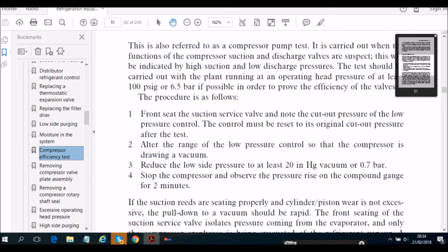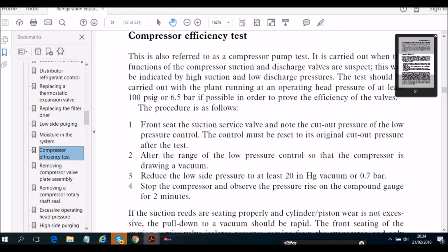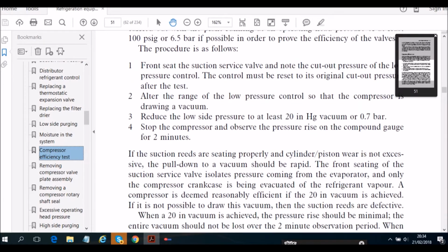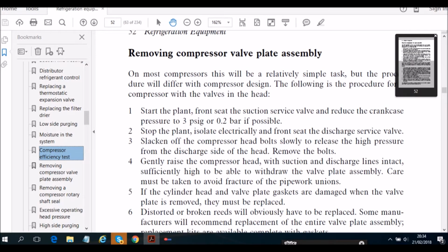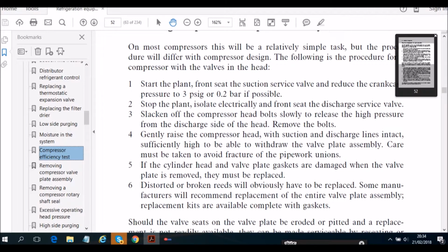Now, I would say to you, never ever front seat a discharge service valve on your compressor unless you can electrically isolate that compressor. So it says here, look, functions of the compressor: suction, discharge, valve, efficiency. Oh yeah, front seat suction service valve. Okay. There is one there. Yeah, this one. Isolate electrically and front seat the discharge. Okay. So in other words, never front seat your discharge service valve unless you've isolated electrically.